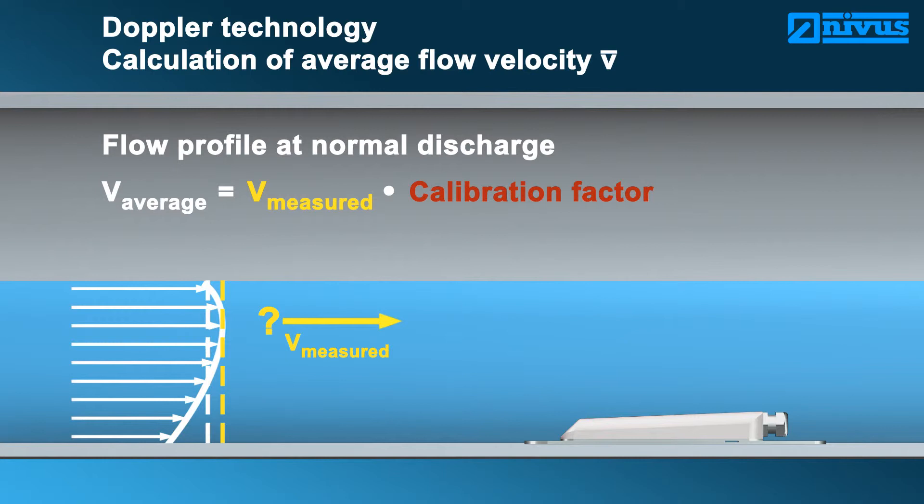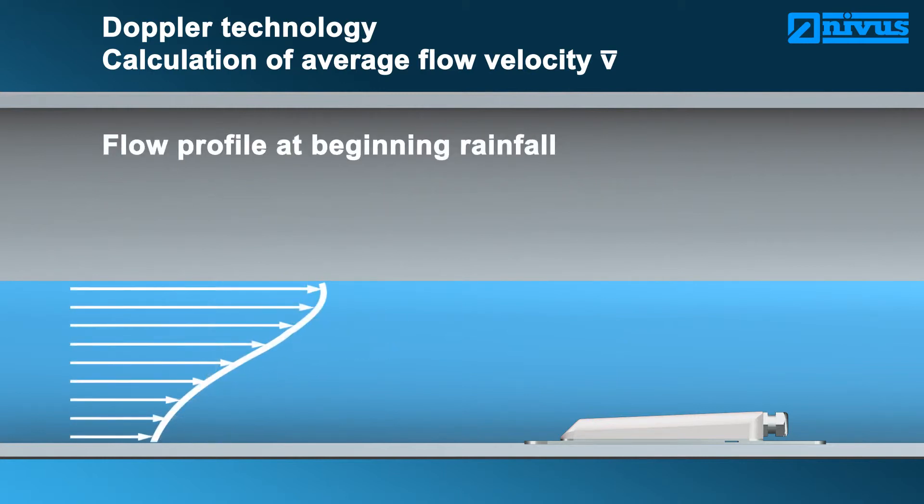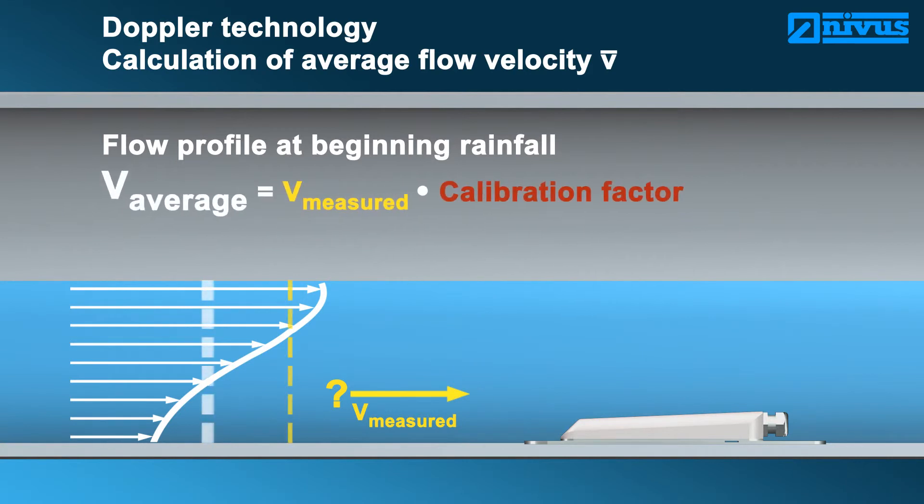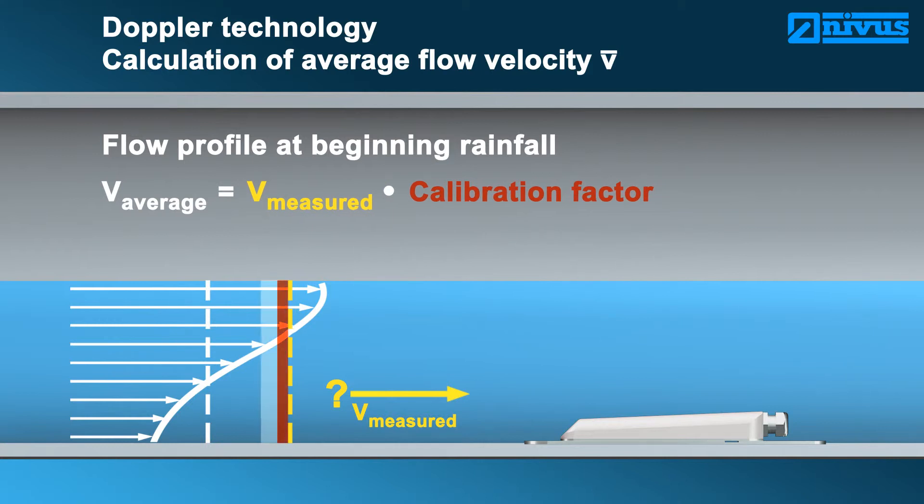The calibration factor is valid only for one stationary condition. If the flow conditions should change, such as due to rainfall, the flow profile will change accordingly. The originally determined calibration factor is no longer applicable and the reading is distorted.